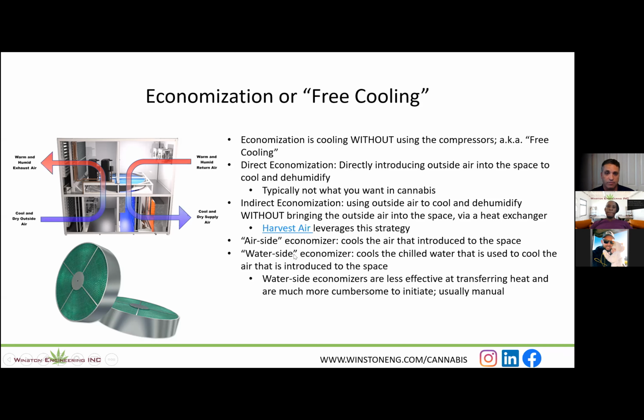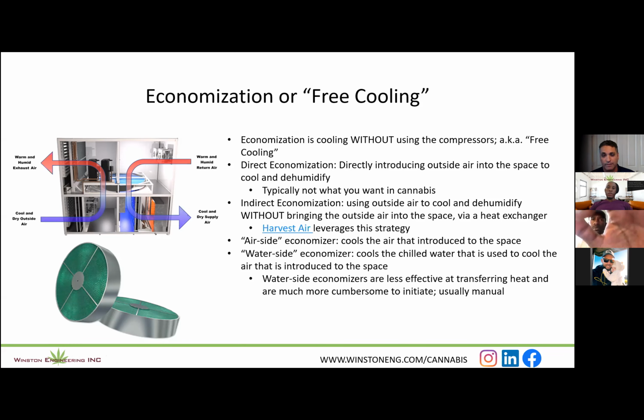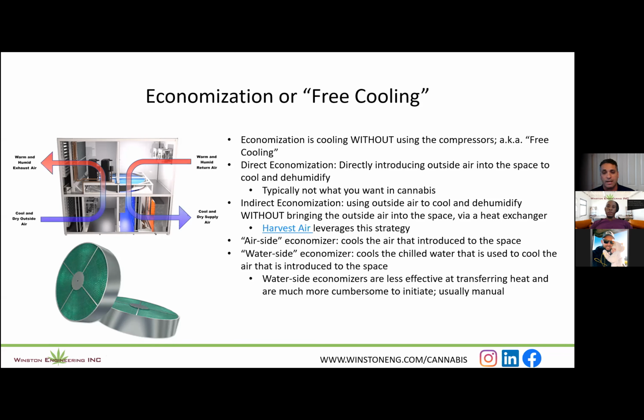There's direct and indirect on the air side. That's when you're using air to cool and dehumidify the space. Water side economizers apply to chill water. Effectively, what water side economizers are is instead of using the compressors to reject the heat, if it is cool enough outside, you can use just the outside air to transfer the heat from that fluid to the outside air.